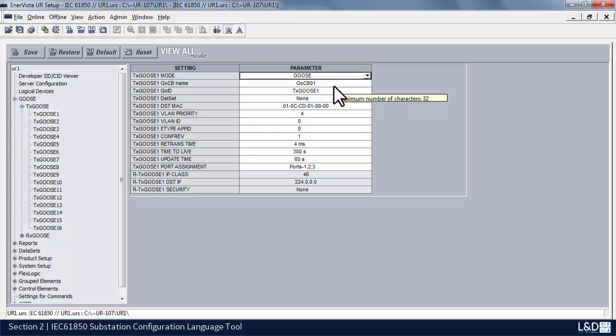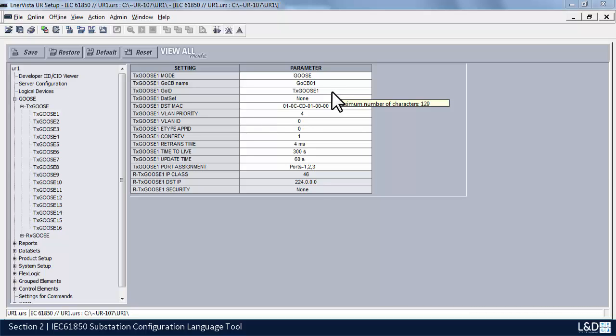The next field is the GOOSE control block. You can see there's a maximum of 32 characters. This GOOSE control block is just a reference as per the standard. The GOOSE ID is the actual name of the GOOSE — the name that subscribers are looking for when they want to subscribe to it. This is very important. The field size is 129 characters.